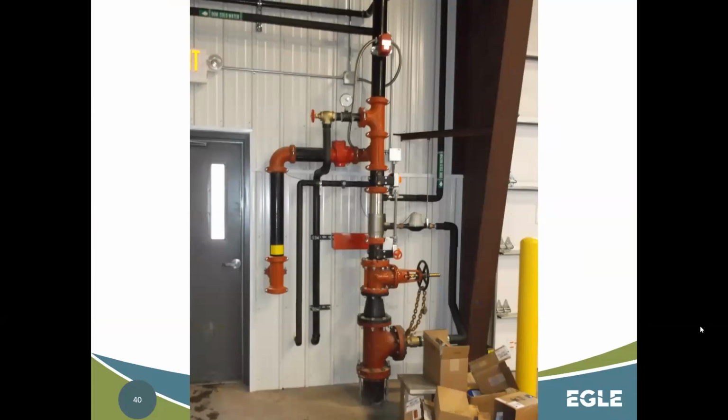One of the things you're going to want to double check is where the assembly is going to be in relation to where we have other plumbing split off. In this case, it's difficult to tell from the picture, but there's a potable water line, and we need to see, depending on where that's plumbed, where the fire suppression is plumbed from, are things actually being protected with where the backflow preventer is.